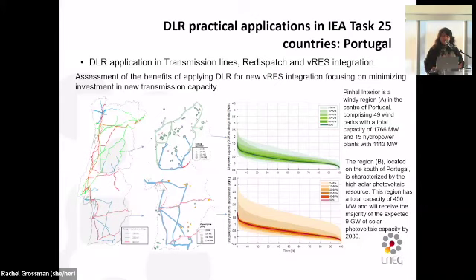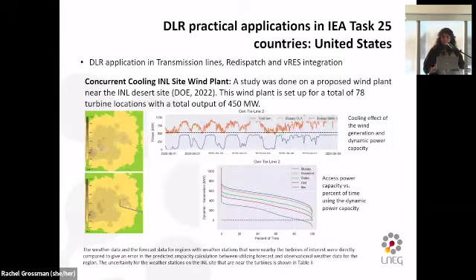Of course, this implies that some control needs to be installed in the wind power plants, because for certain precise conditions we may not have enough capacity to transmit all the generated power. If we look at the bottom image, it shows a region of Portugal where the solar resource is extremely high. And what this graphic tells us is that almost 100% of the time, we have a very large extra capacity in the lines if we want to use it.